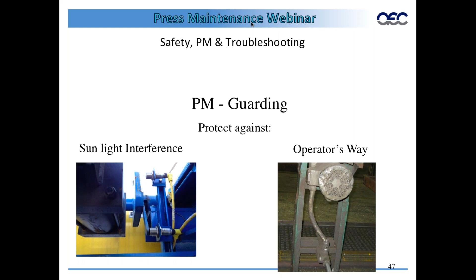On the right, this is very common: so much flex conduit is used in the plant, and over time it often gets hit and broken. The metal inside the flex conduit is very sharp, so it can easily cut the wire. Look for signs of this damage, replace it, and try to guard against it happening again.